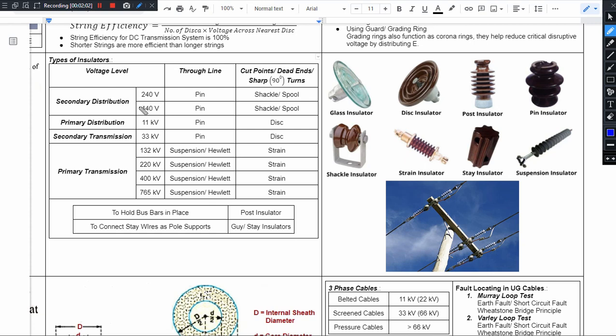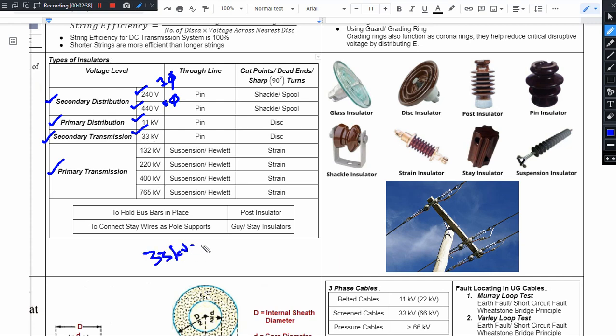Usually in transmission and distribution, we have four voltage levels: primary transmission, secondary transmission, primary distribution, and secondary distribution. Secondary distribution starts with 240 volts (single phase) and 440 volts (three phase). 11 kV lines are called primary distribution, and 33 kV lines are called secondary transmission. Any voltage greater than 33 kV is called primary transmission.